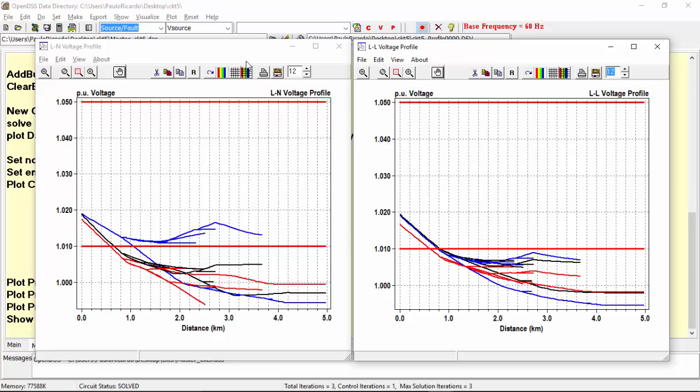These two voltage levels are the norm VmaxPU, that is the maximum permissible per unit voltage, and the norm VminPU, the minimum permissible per unit voltage, respectively. By default, these parameters are 1.05PU and 0.95PU, but I have set norm VminPU to 1.01PU a few moments ago, to show you the three voltage levels defined by norm VminPU and emerg VminPU in the circuit plot when the lines represent voltages.